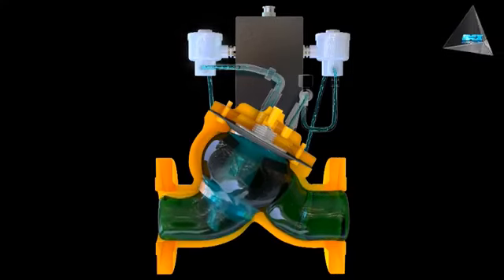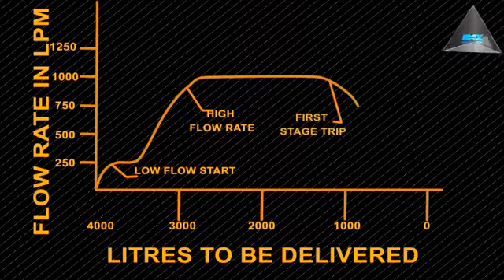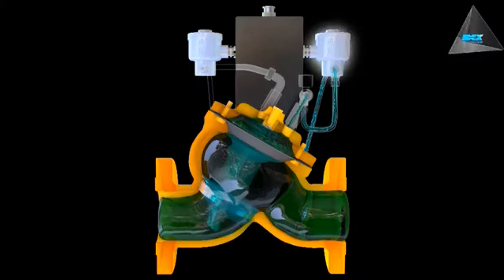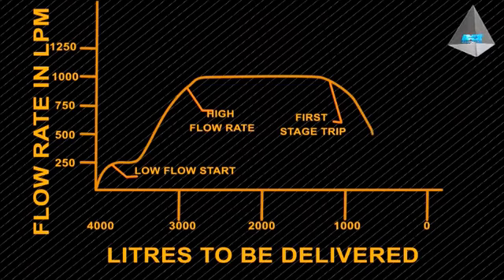De-energize NC. Flow starts reducing. Flow rate can be further reduced by de-energizing NO momentarily and energizing it again immediately. De-energize NO. Valve fully closed.